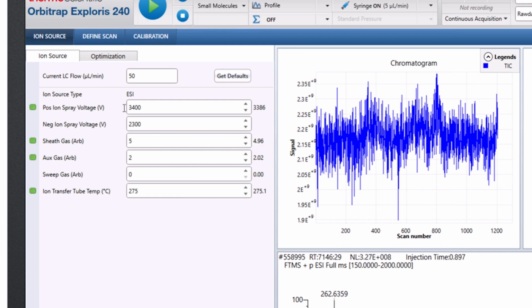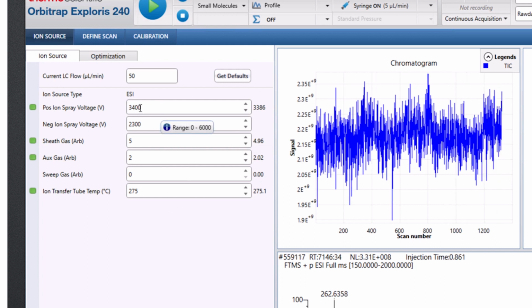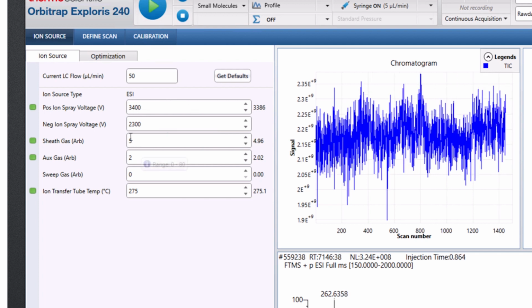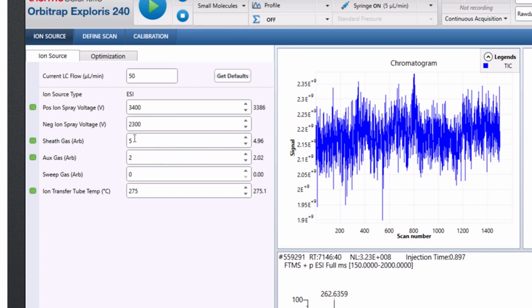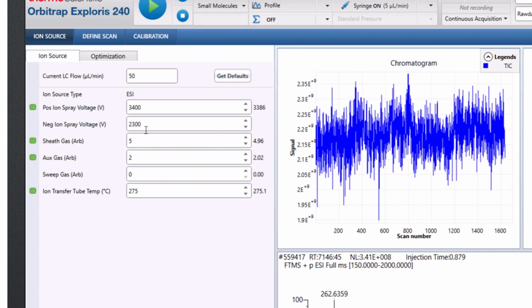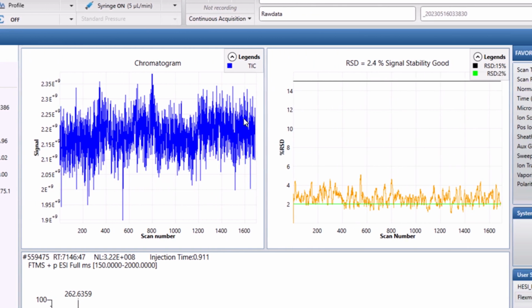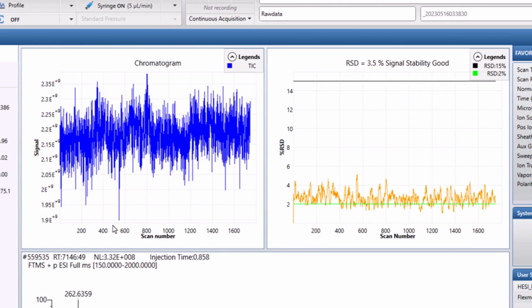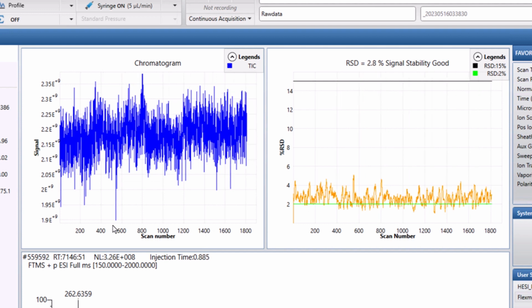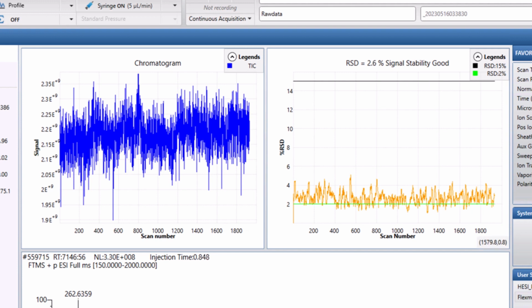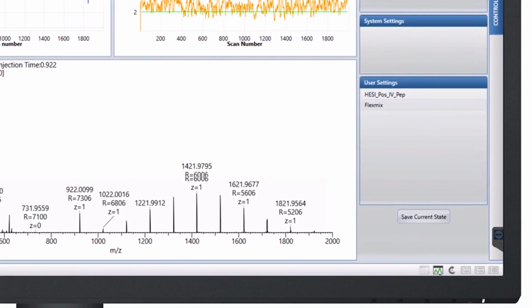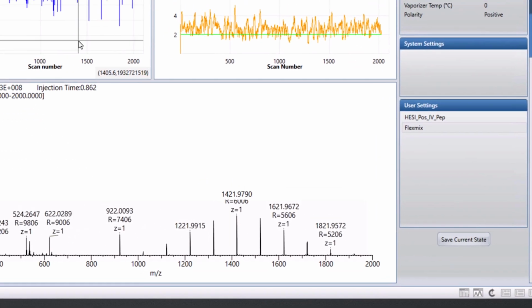Another thing you can do is adjust the voltages. So maybe you need to taper off on your voltage or increase your voltage, and that will help, or play around with the gas settings. But most of the time, once you know your mass spec well, you should be able to preload those settings, go back to the settings that worked last time, keep a log. That's also a helpful tip. And then get nice spray stability. So I'm happy with this. It's less than 5%. I'm going to go ahead and stop monitoring it.